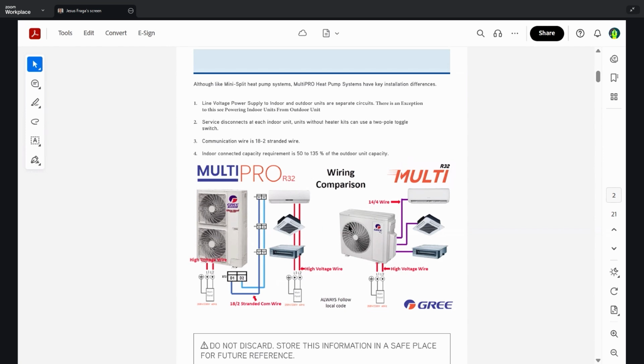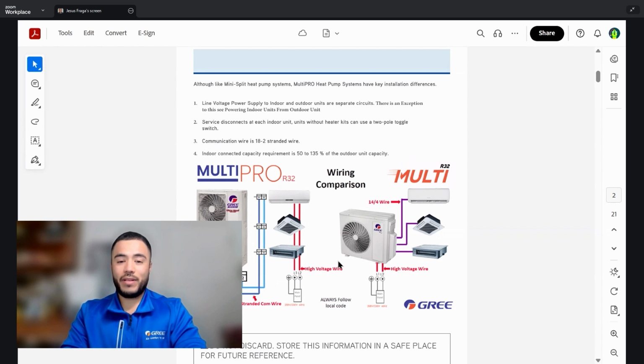The main difference here is pretty much the communication method that is used. One will use the 14/4 as I stated, and another will use the 18/2 stranded communication wire. Now with R32 MultiPro, there's an added feature where you can actually power the indoor units via a terminal block at the outdoor unit. And we'll see that on the next page below.